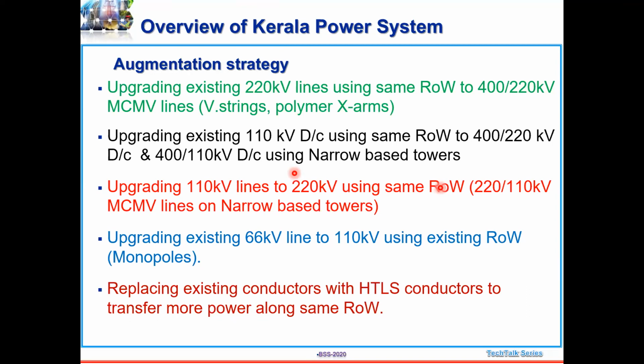And again, we are going for reconducting of the existing ACSR conductors with high temperature low sag conductors, HTLS conductors, which have a higher current carrying capacity, around 2 to 2.5 times more than the ACSR conductor, with which we can use the same towers. You don't have to replace the towers for using the HTLS conductors because they have the same mechanical properties as the ACSR conductor, but they have very low sag also. Because normally when you load the conductor more, the sag will increase. That's basically a problem for loading. But for the HTLS conductors, you don't have any sag problem because the sag is very small.